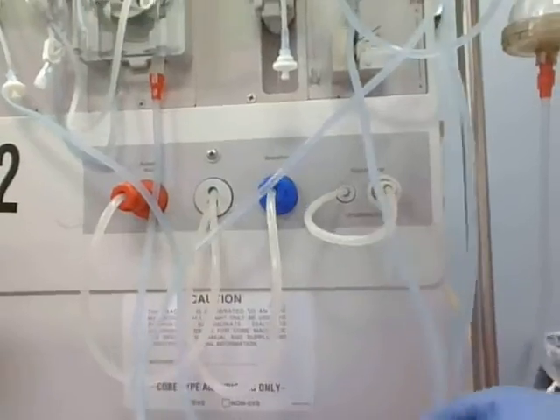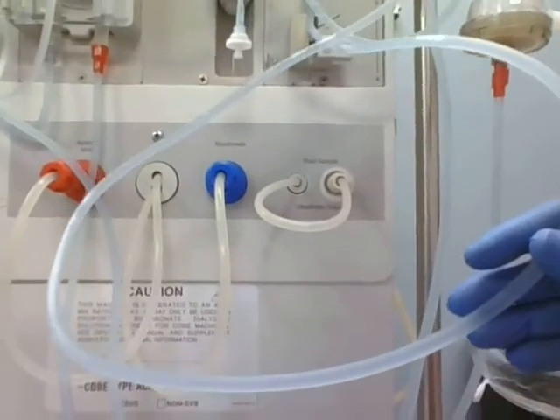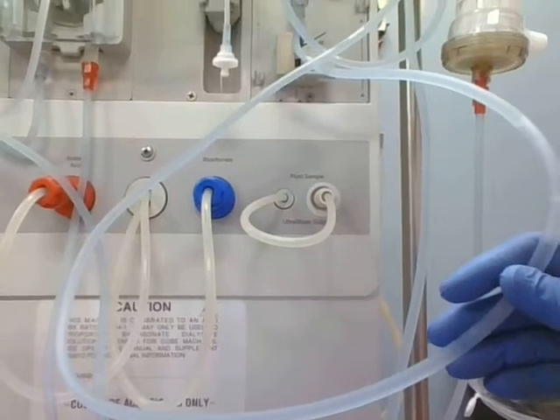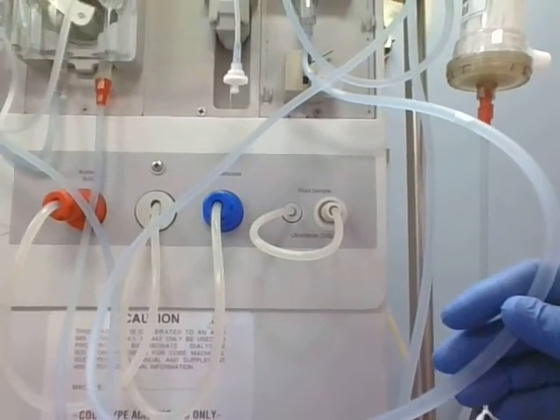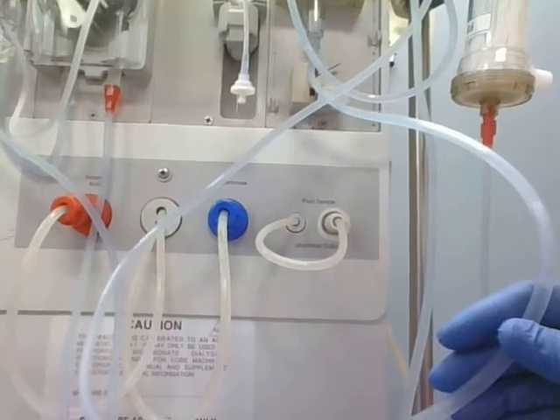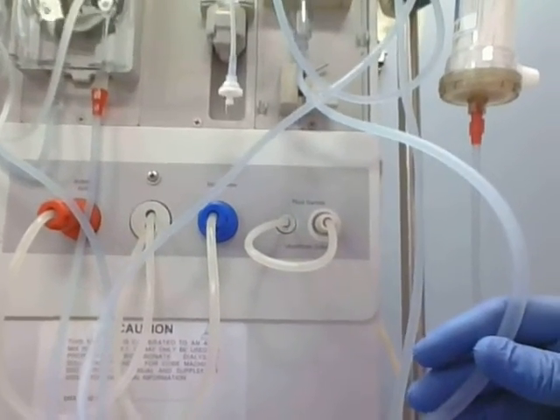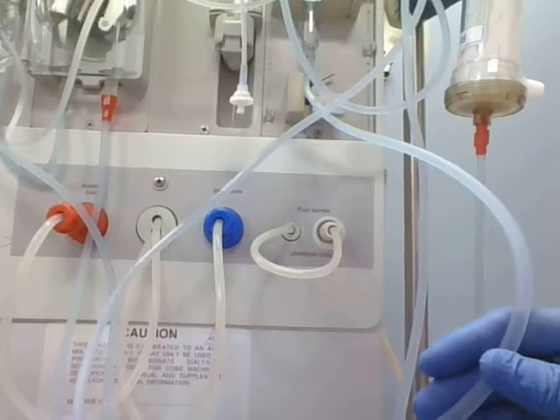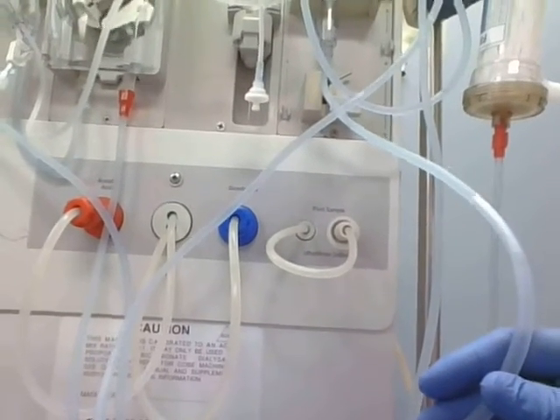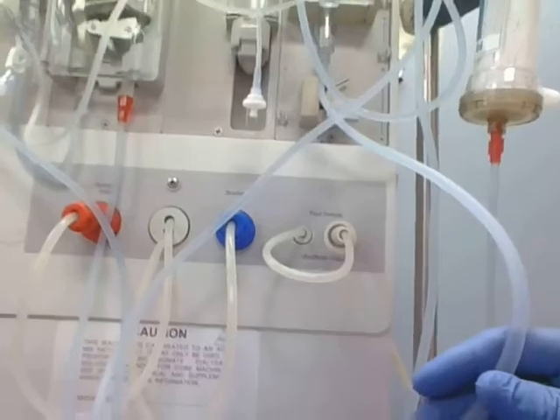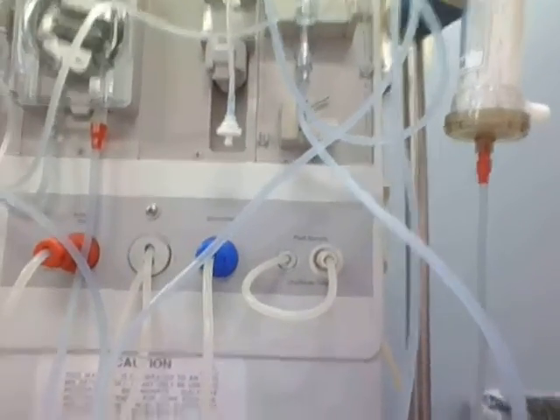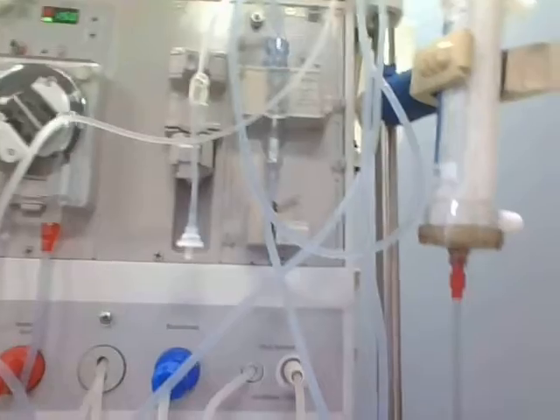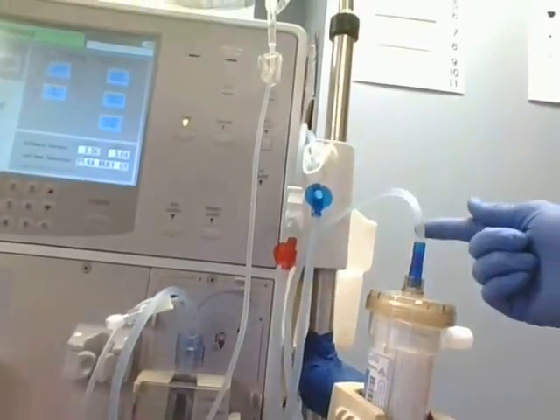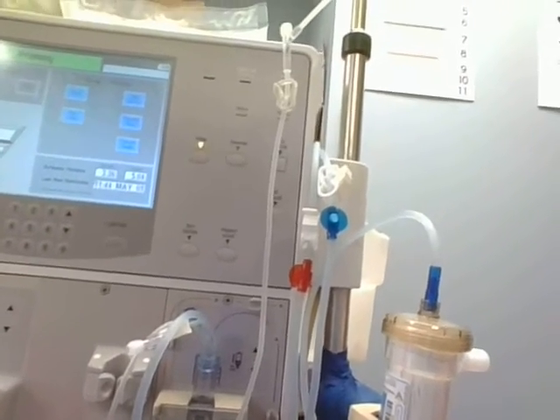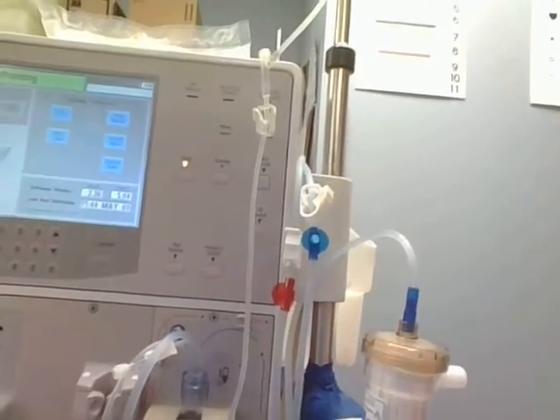So if you can see the bubbles moving through here, and you can see them moving up and down, this is the venous line. And if the blood pump were not moving, then we would not be getting any saline through this line. So the peristaltic action of that blood pump moving pushes the saline through our line, and it comes up through our venous blood port.